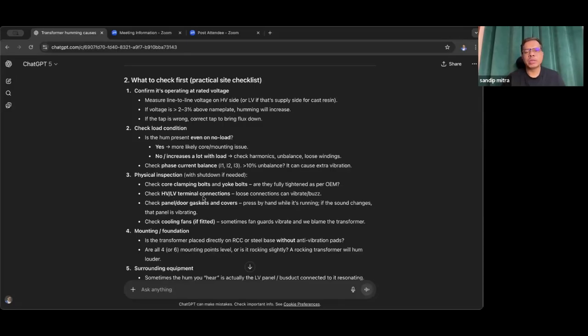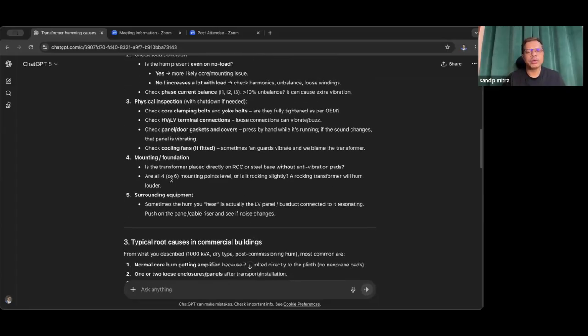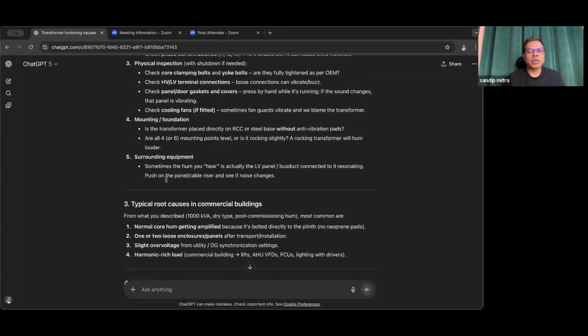Check HV and LV terminal connections. Check panel door gaskets and covers. Check cooling fans if fitted. Then the mounting and foundation. Is the transformer placed directly on an RCC or steel base without anti-vibration pads? Are all 4 or 6 mounting points level, or is it rocking slightly? A rocking transformer will hum louder, as will surrounding equipment. Sometimes the hum you hear is actually the LV panel or bus duct connected to it resonating. Push on the panel or cable riser and see if the noise changes.